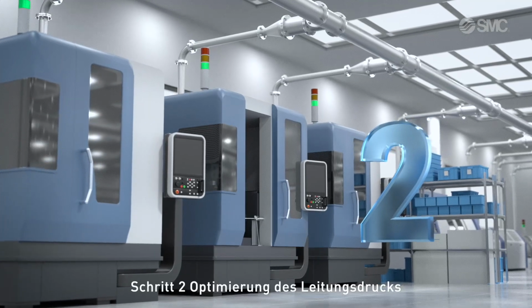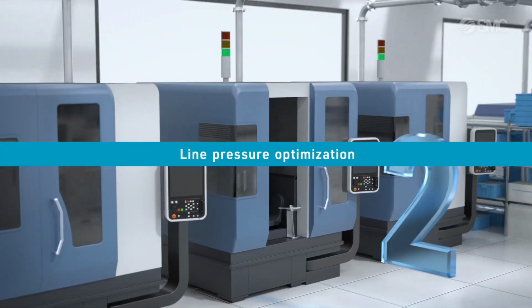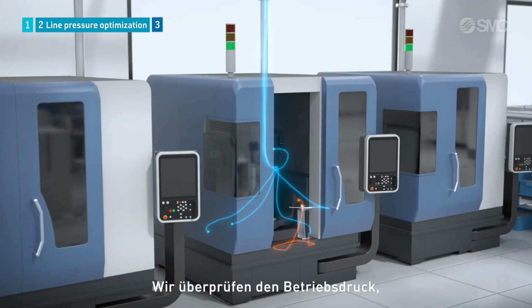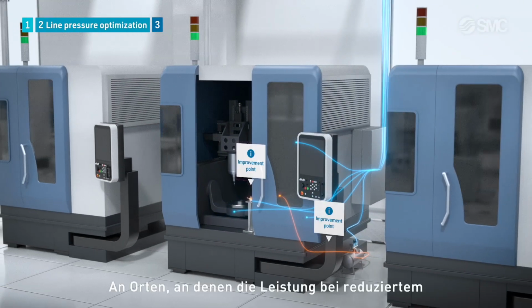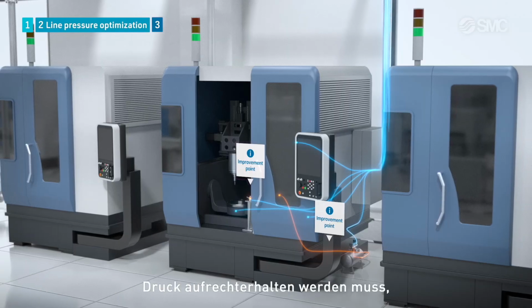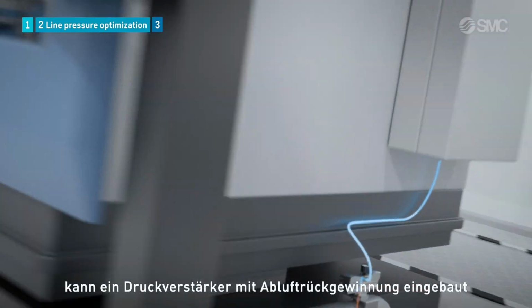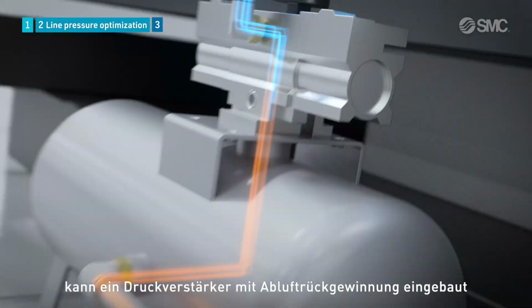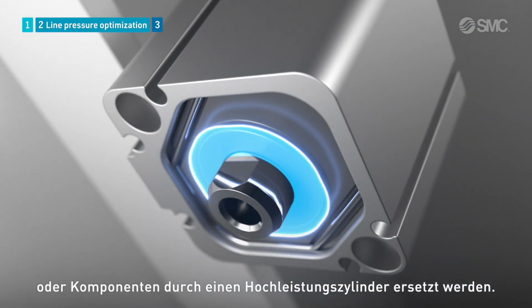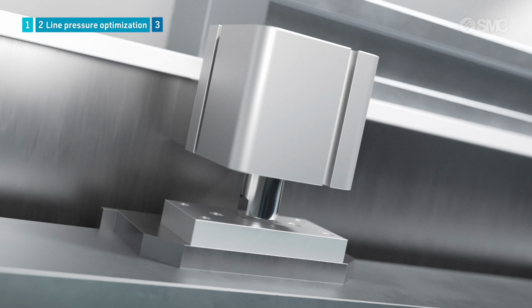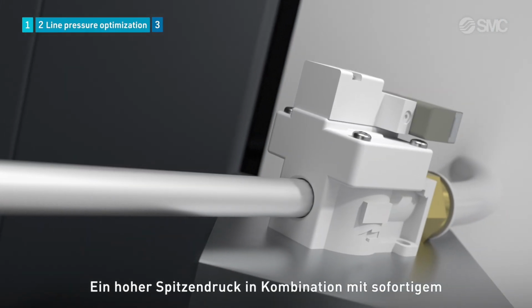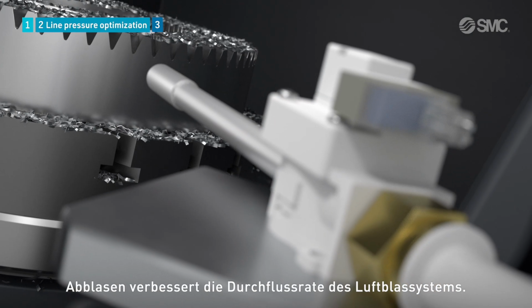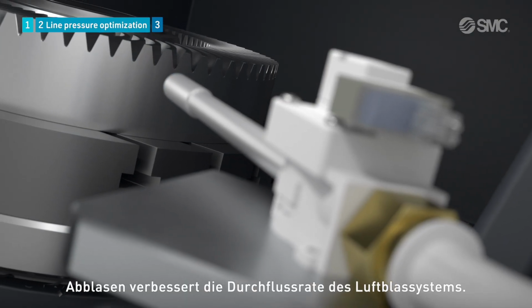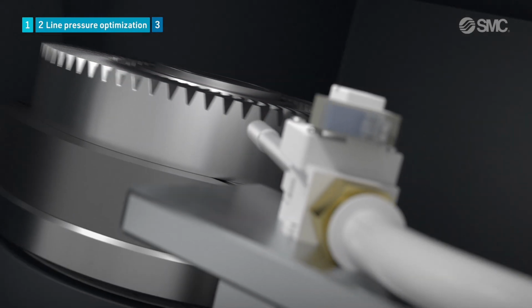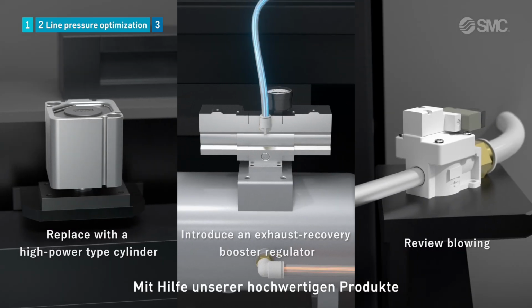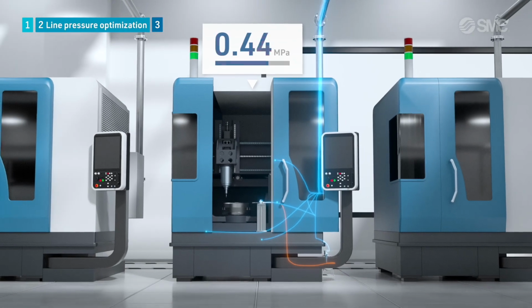Step 2. Line pressure optimization. We verify the air pressure that can maintain production efficiency. In locations where the output must be maintained while the pressure is reduced, we can introduce an exhaust recovery booster regulator or replace parts with a high-power type cylinder. In addition, the flow rate of the air-blowing system can be improved by utilizing high peak pressure and instantaneous blowing. By introducing optimal products, we optimize the line pressure.